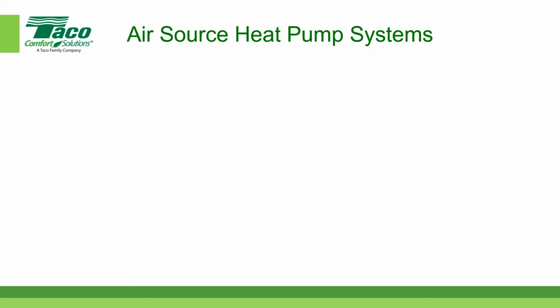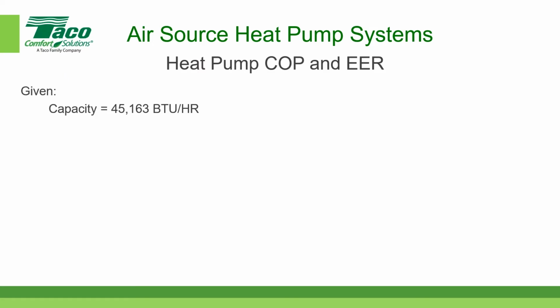All right, so let's do a quick example here. Let's say we had 45,163 BTUs per hour, and with the energy input of 5,510 watts, we want to find the coefficient of performance. So it's basically the output capacity divided by the energy input, but they have to be in the same unit. So I have to first convert the 45,163 BTUs into kW, and I have to convert the input power, which in this case is 5,510 watts, into kW. Once I get both the capacity and the energy input into the same units, I simply divide the two, and that's what gives me the coefficient of performance.